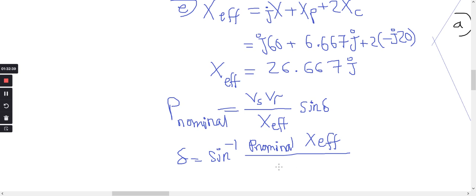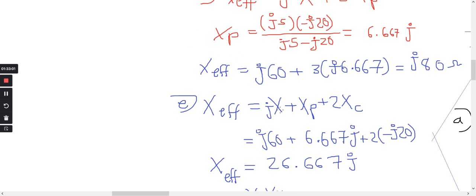Okay, so delta equals sine inverse of P nominal. What was P nominal? From the first step, it was 597.558, about 598, times the effective impedance as an absolute value, 26.667, divided by Vs times Vr, 230 times 220, line values. So delta is how much? Sine inverse of 597.559 times 26.667 divided by 230 times 220. Which is that? Then 180 times this divided by pi. How much?